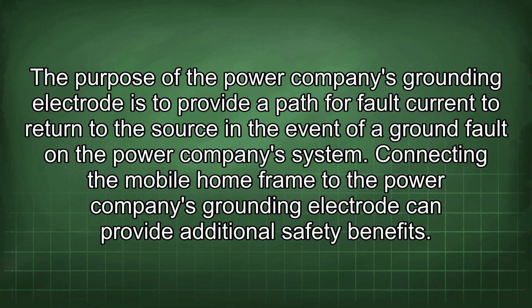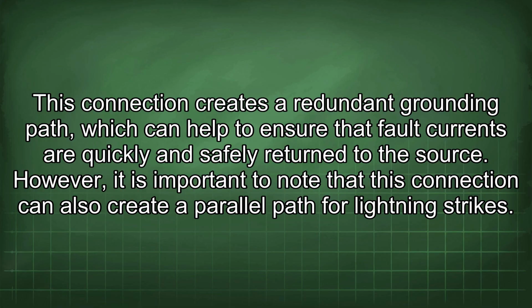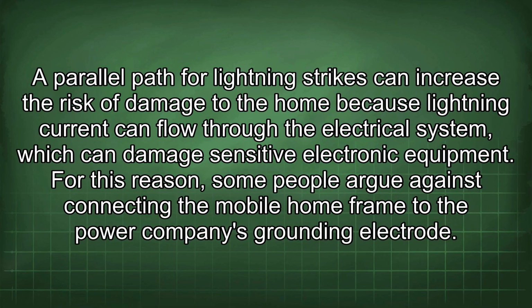Connecting the mobile home frame to the power company's grounding electrode can provide additional safety benefits. This connection creates a redundant grounding path, which can help to ensure the fault currents are quickly and safely returned to the source. However, it is important to note that this connection can also create a parallel path for lightning strikes. A parallel path for lightning strikes can increase the risk of damage to the home because lightning current can flow through the electrical system, which can damage sensitive electronic equipment.